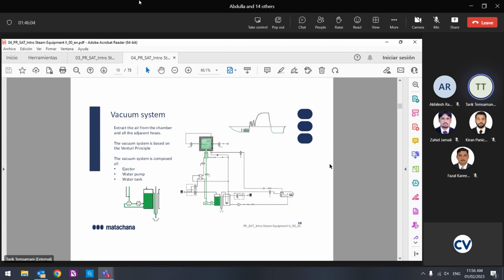So if we don't reach this pressure, there is a leak, and the leak can come from any connection in the chamber. Or the non-return valve is not opened correctly, the pneumatic valve is not opened, the ejector is not good and it's dirty, the vacuum pump is not working well, the temperature is high, the gasket. There are many possibilities. So we need to check all these possibilities.